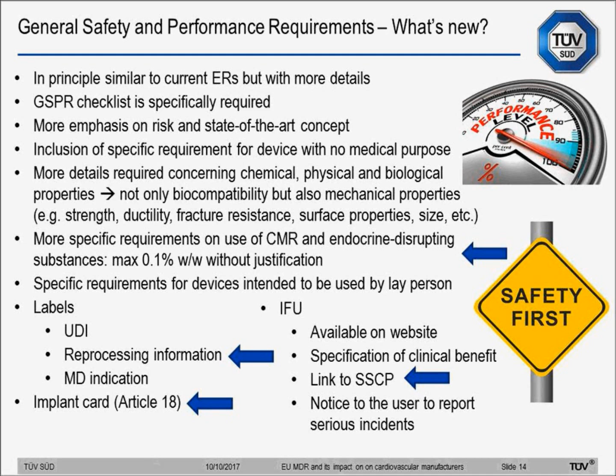There is no time to go into the fine details of each requirement today. However, I think it's important to mention to manufacturers of cardiovascular devices the more specific requirements regarding substances that might be carcinogenic, mutagenic, or toxic to reproduction, with a clear threshold introduced, which is 0.1% weight on weight. There are also new requirements for labels and for IFU, which include reprocessing information if the device can be reused, and an implant card for devices intended to be permanently implanted.